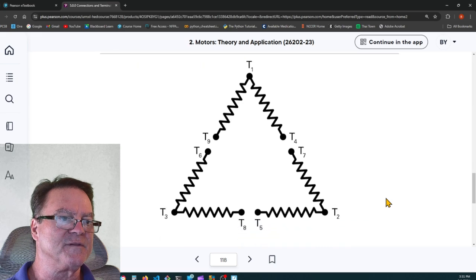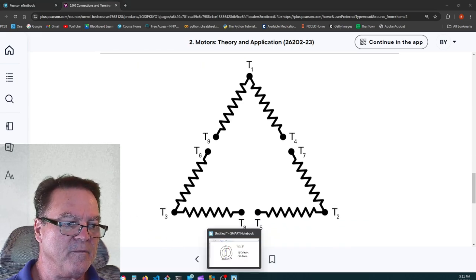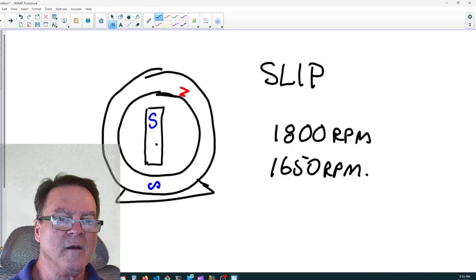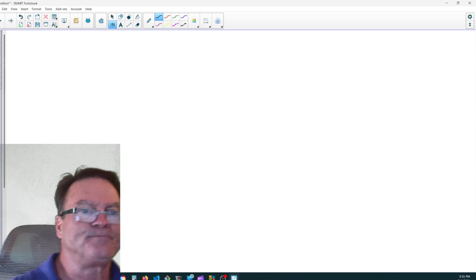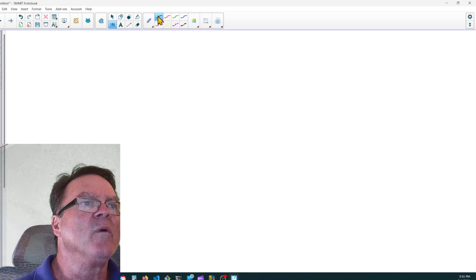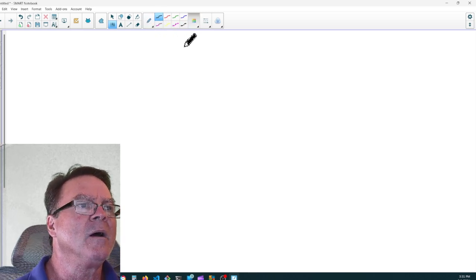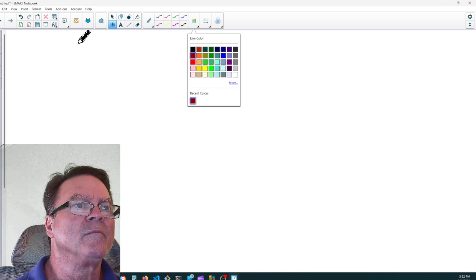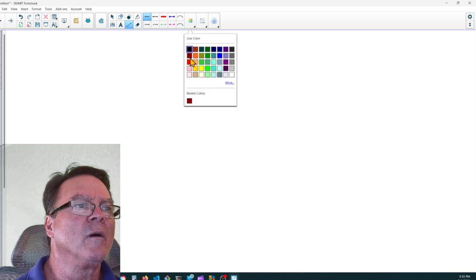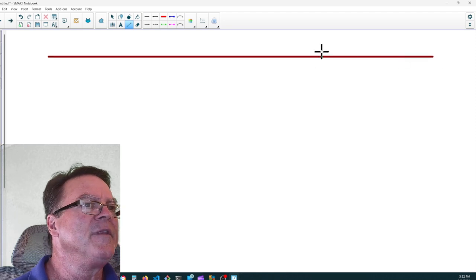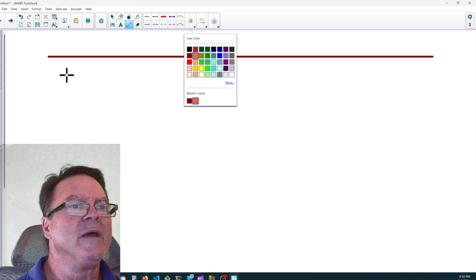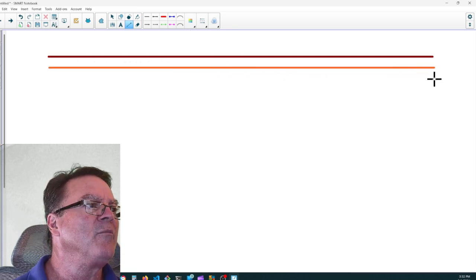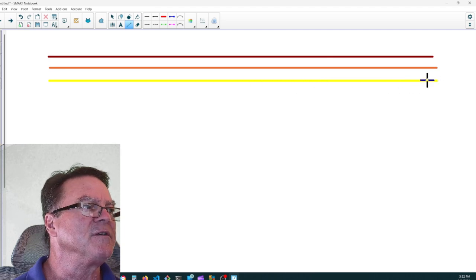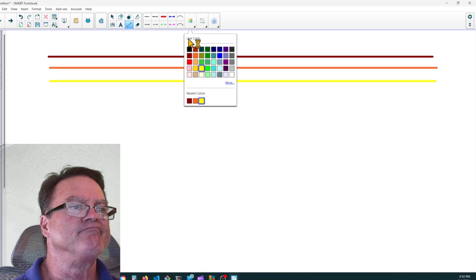All right, let's go ahead and talk about this, because inquiring minds want to know. So again, what we said is that I'll try to use brown or yellow. There. These are our high voltage incoming lines. Brown, orange, and yellow. Black, red, blue is for 120, 240. Brown, orange, yellow is for 240, 480. I'm not going to bother with the ground, so we're not going to show the ground.